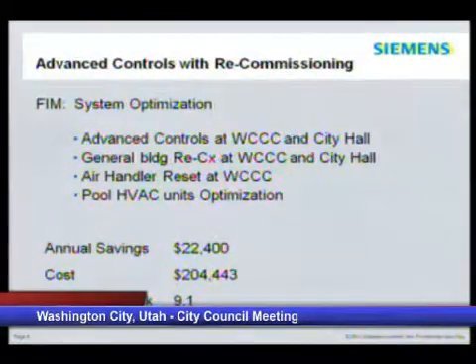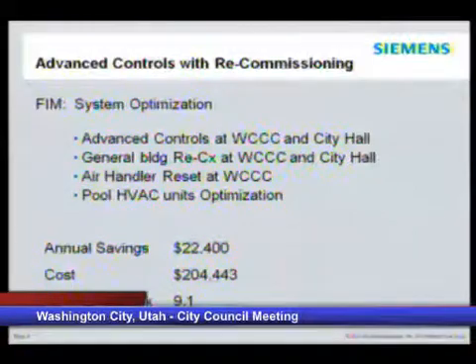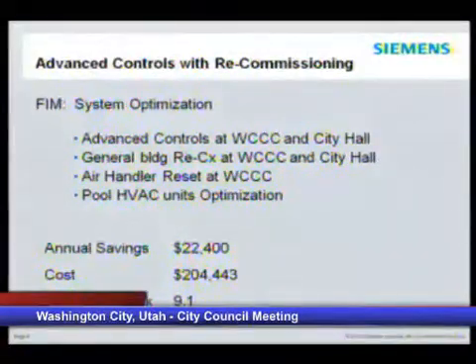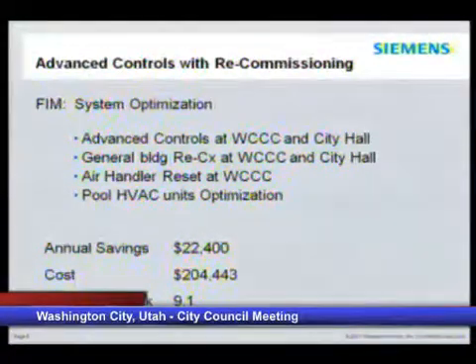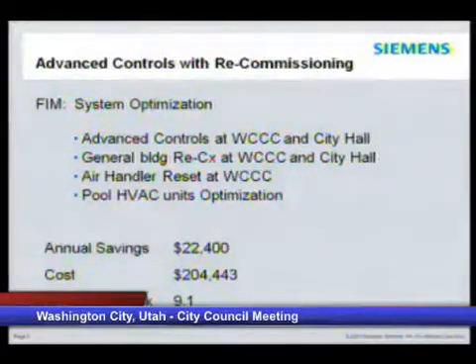That's correct. An example might be the supply air temperature sensor in your registers here. That's feeding back a signal to your control system. It's telling you what degree air is coming out, right? So we would reuse that sensor. We'd make sure it's still there, number one, and that it's reading the correct temperature, number two. But we can reuse some of those components like a temp sensor.